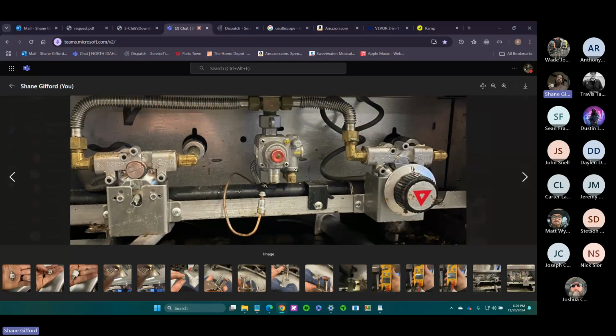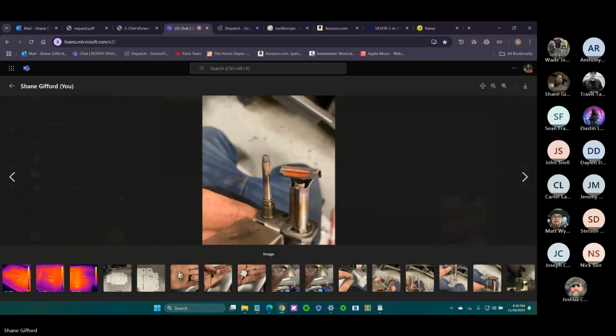So if I got a call that the fryer or the griddle or the oven or anything that is gas fired and has a gas valve and a thermocouple is not working, then usually the first thing I'm looking at besides power, is it plugged in? Is the gas valve open? Did somebody shut the gas off to the appliance, or is it open? First thing I'm going to do is start at one burner and progress your way forward. The most common problem, like I said, is this guy right here. These do just get dirty over time. They have to be cleaned.